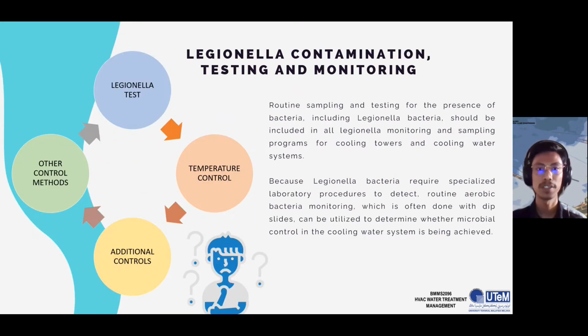Okay, next. Legionella contamination testing and monitoring. Routine sampling and testing for the presence of bacteria, including Legionella bacteria, should be included in all Legionella monitoring and sampling programs for cooling towers and cooling water systems, because Legionella bacteria require specialized laboratory procedures to detect. Monitoring of aerobic bacteria, which is often done with dip slides, can be utilized to determine whether microbial control in the cooling water system is being achieved. There are several types of contamination testing and monitoring, which are Legionella test, temperature control, additional control, and the last one, other control methods.